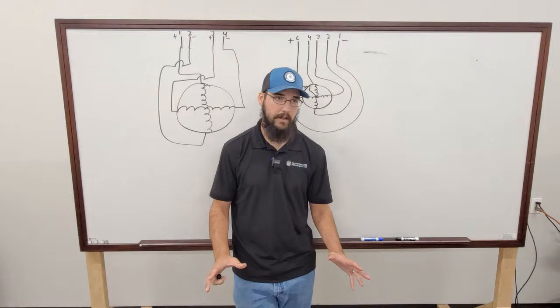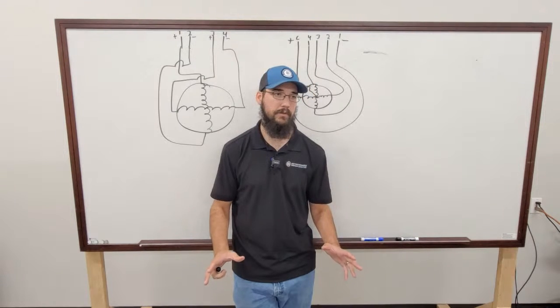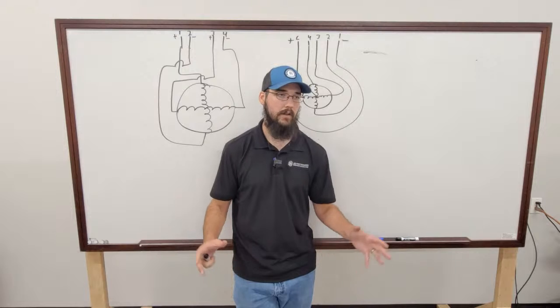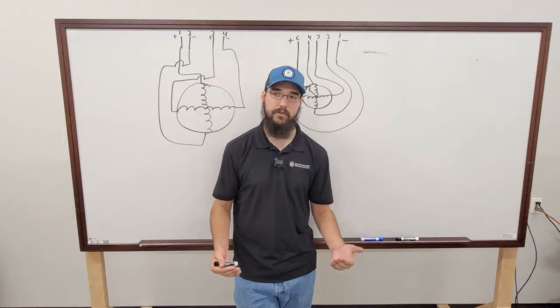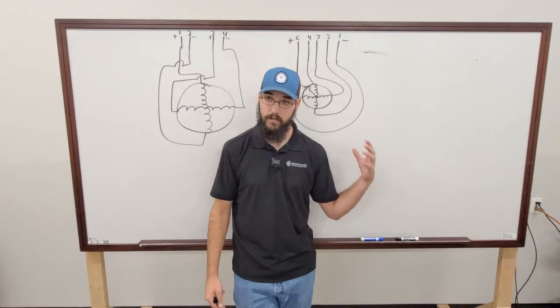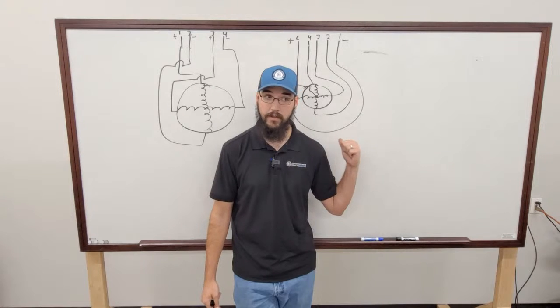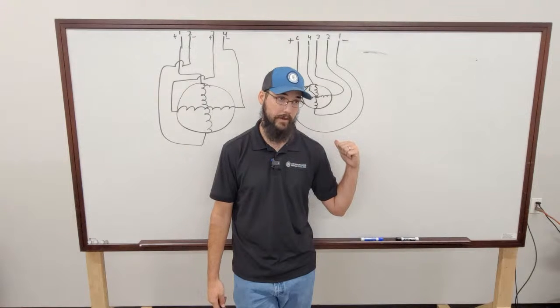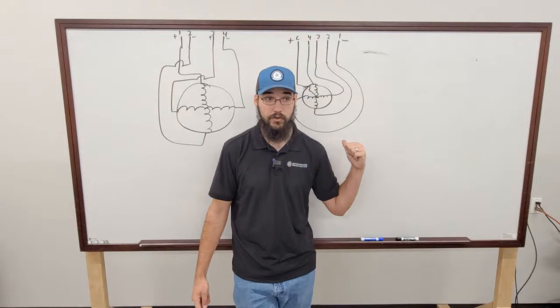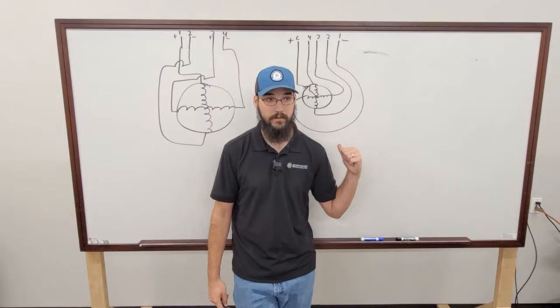Ultimately, EXVs are pretty simple devices. If you're worried about an electrical failure, if you have resistance and nothing is shorted to ground, and your winding to winding resistance is on point, it should work electrically. But that's not to say your threads are bad or anything like that.